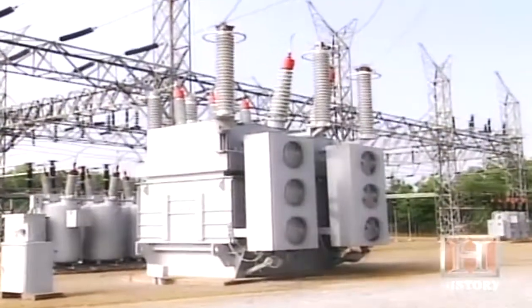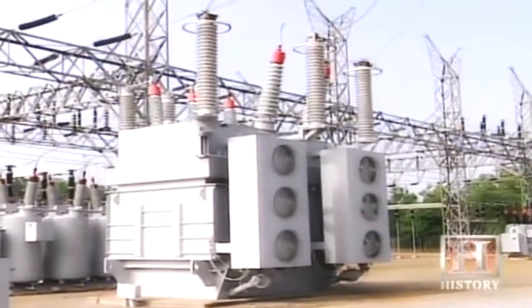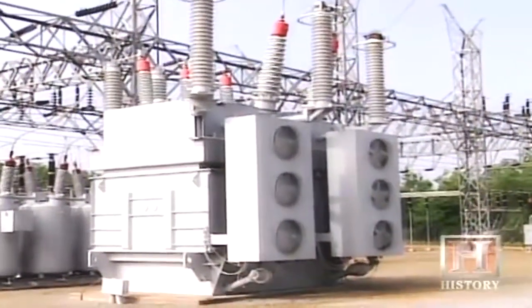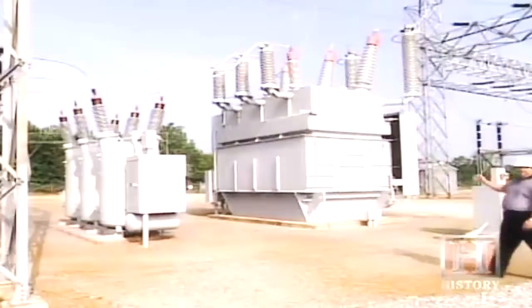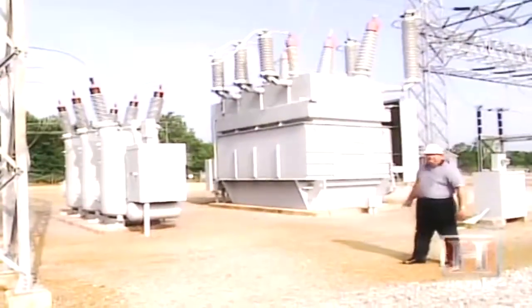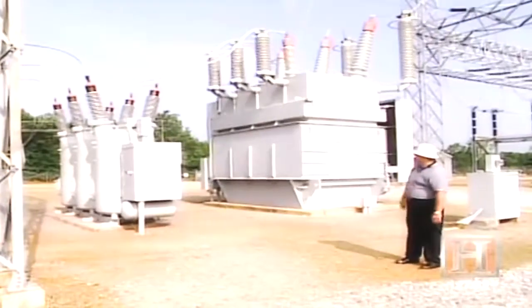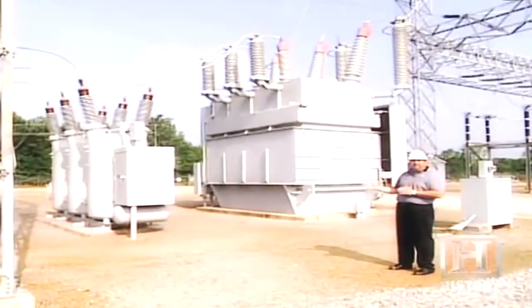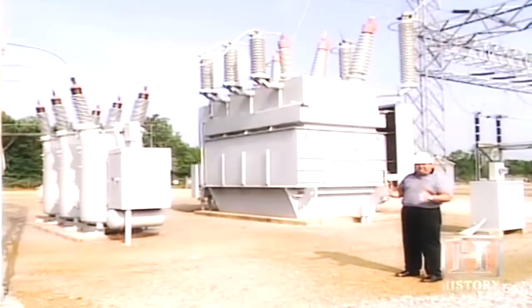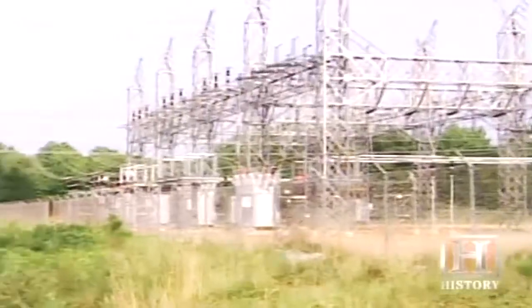Transformers at the substation alter the voltages so that electricity can be routed where it needs to go. We're standing in front of the 230 to 115 kV transformer, the big box here. The transformer converts the 230 kV voltage down to 115,000 volts and then supplies power to the 115 bus, which is then shipped out across the 115 kV grid.